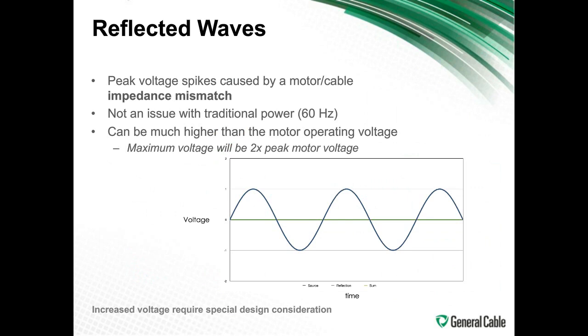Another phenomenon that we need to talk about is reflected waves. Reflected waves are another aspect of the high frequency modulation and the rapid rise times that are causing issues with the VFD system. Peak voltage spikes are caused by the impedance mismatch I was talking about earlier, which is not an issue for 60 hertz traditional power systems. But when you have the high frequency drives, you are creating pulses of voltage going through, and at the same time you're getting a reflected wave that comes back.